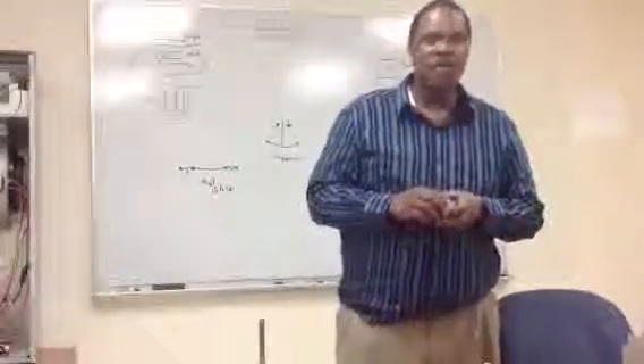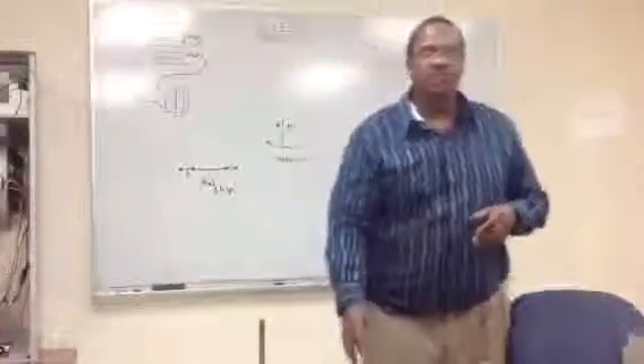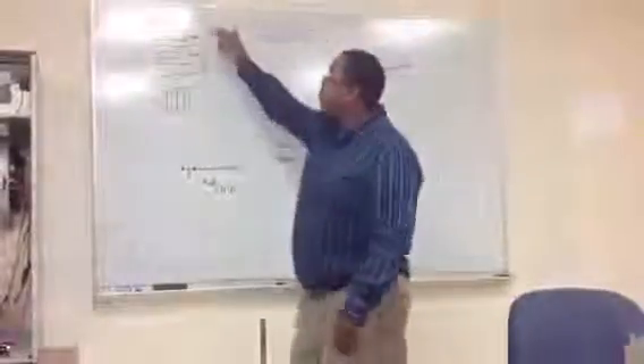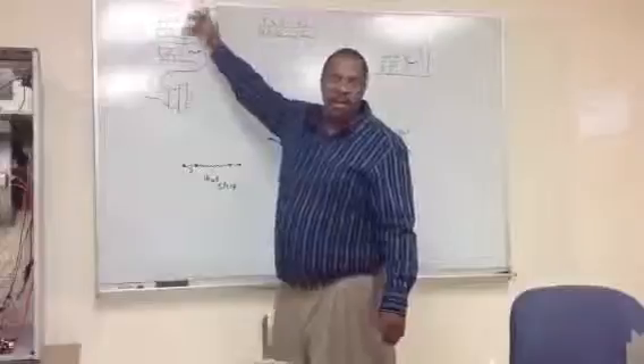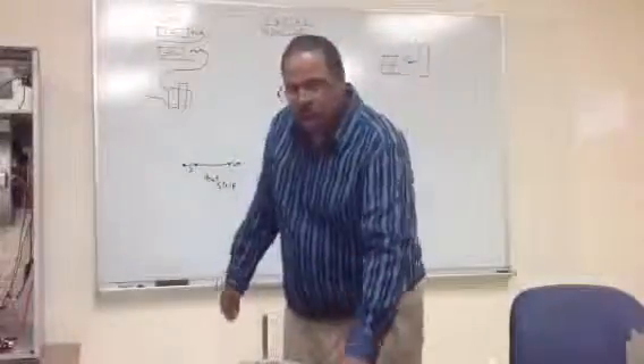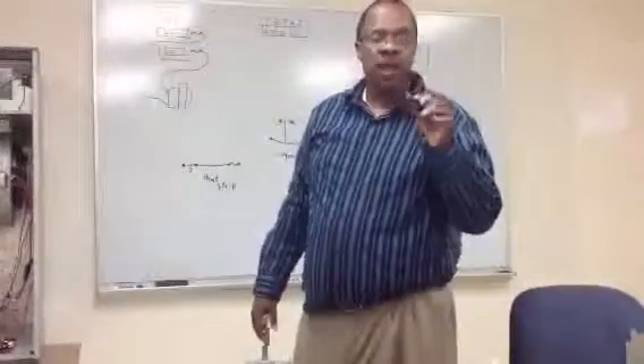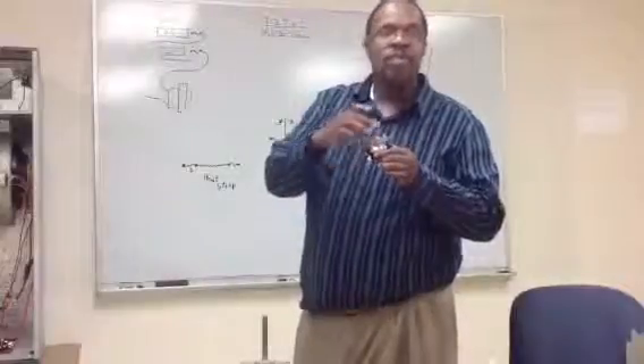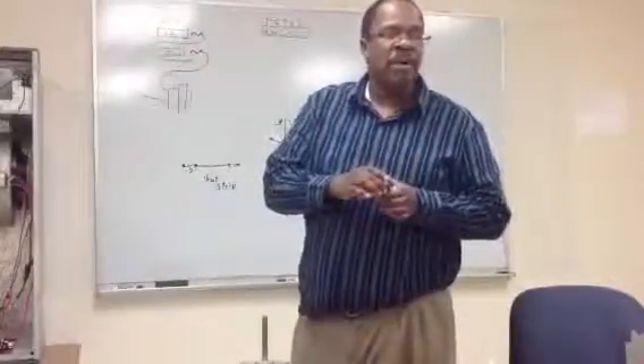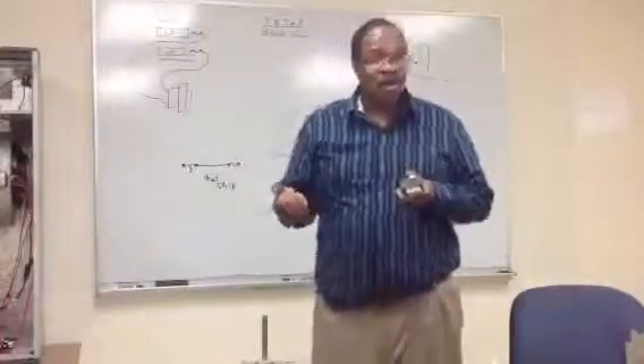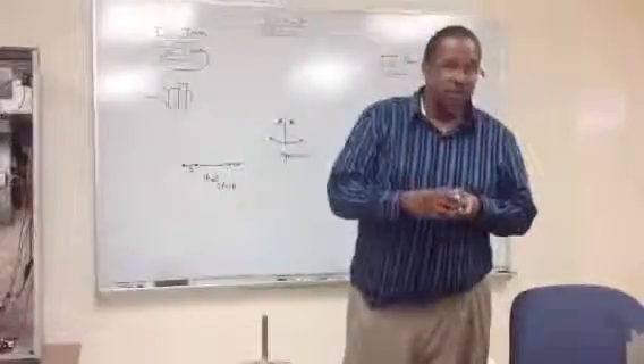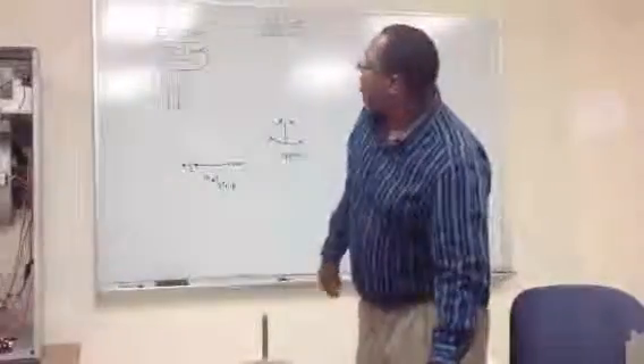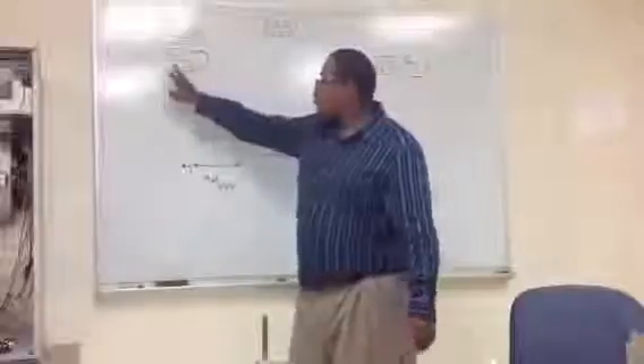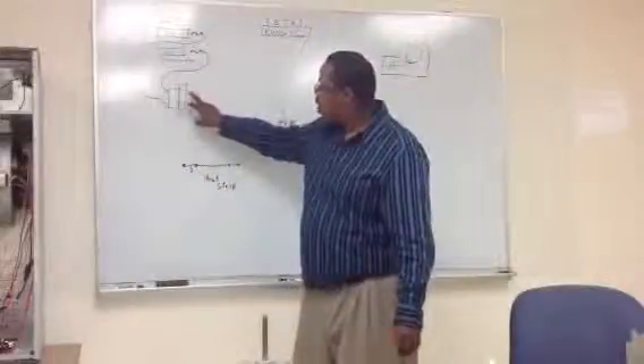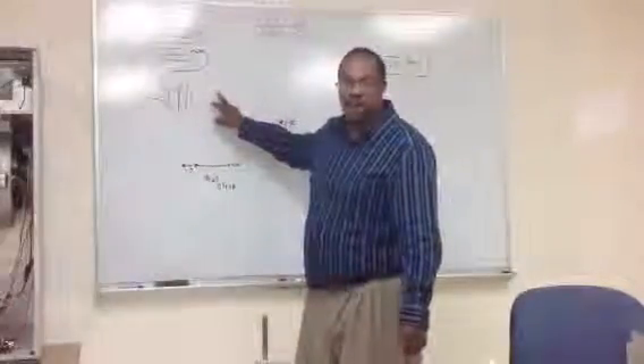So it's very important. In this building right here, we use 208 voltage, not 240. So if I was wiring up this transformer, I would wire it up with 208. I would use common plus the 208 tap. If I was in a building that used 240, I would use common plus the 240 tap. Anyway, we'll wire our transformer up, and now it will step down the voltage to feed our low voltage controls.